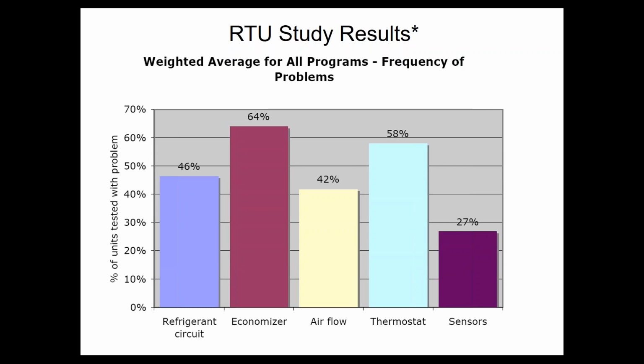And there's quite a few studies out there, including the one on the screen. This one here showing 64% of economizers are not functioning correctly in the field. Right? And this is 500 rooftop units at 180 buildings. Right? And there's other ones like this. The Honeywell similar study showed 70% of economizers are not working correctly. And remember, Honeywell is the one controlling the economizers, and they're telling you that things are getting messed up in the field.